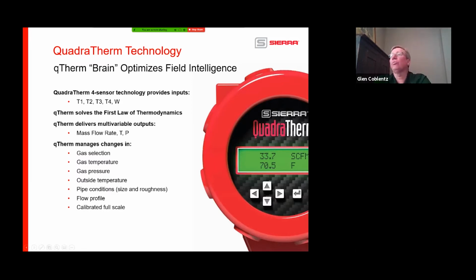Now, everybody else's thermal mass flow meters, including our legacy products, are based on a Wheatstone bridge. So it's one application, one calibration, maybe a little bit of hocus pocus here and there where you can make some changes, but it's very, very limited. And if you do make changes, you start to lose accuracy fairly dramatically. But the Q-Therm brain keeps track of all of this stuff and is delivering the most accurate mass flow measurement that you can get.